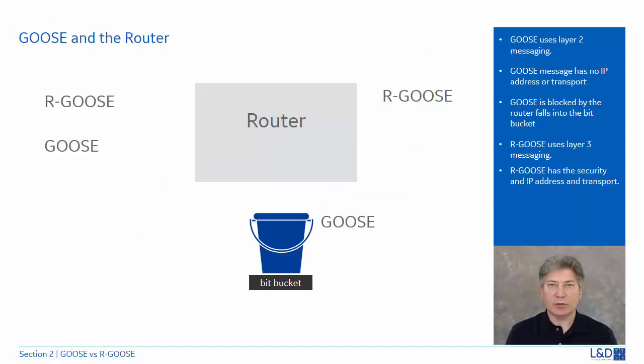Let's take a look at what happens to a standard GOOSE and a routable GOOSE when they reach a firewall on a router. The standard GOOSE is a multicast layer 2 messaging service originally intended for use only within a LAN environment. GOOSE messages don't have an IP address or transport capabilities. When it reaches a router, the firewall doesn't know what to do with it and drops it into a bit bucket, essentially blocking it from getting past a router.